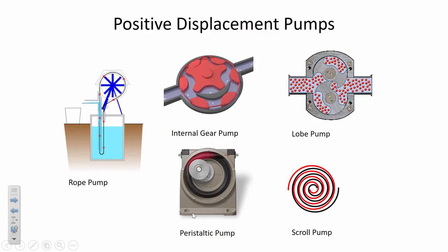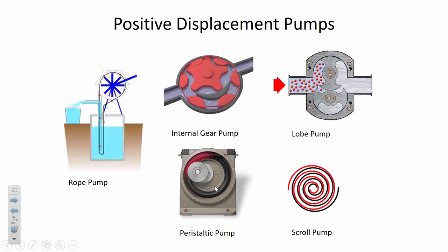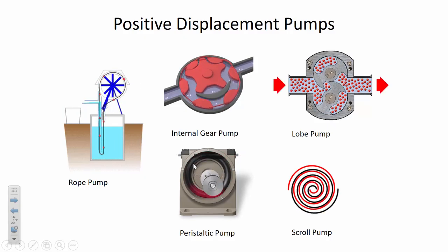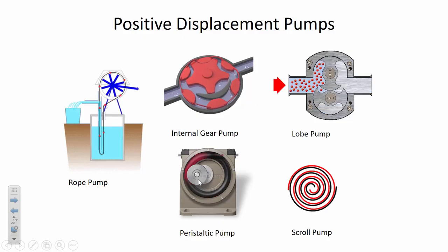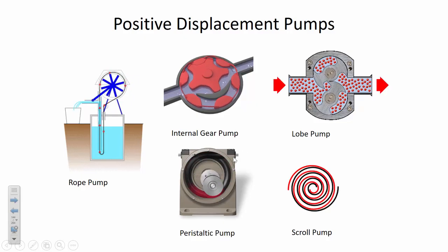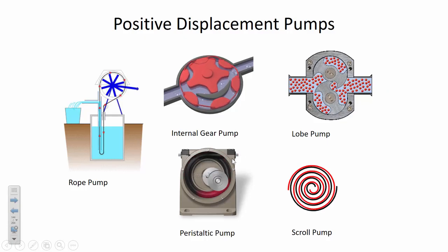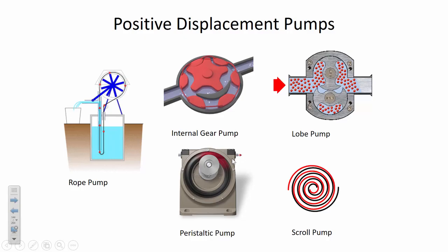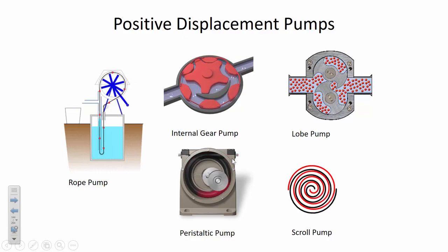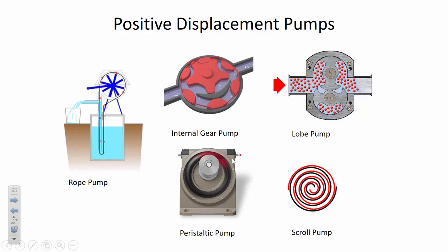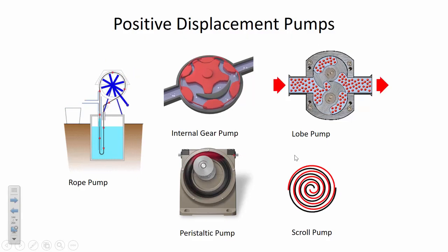Peristaltic pumps are common in environmental or water quality labs. A roller presses against plastic tubing at a certain speed, pinching it to deliver a precise volume of water — as little as milliliters per hour in a very controlled fashion. When you need to deliver a reagent at a very controlled and slow speed, peristaltic pumps work well for that. The more exotic pump types are uncommon in practice.